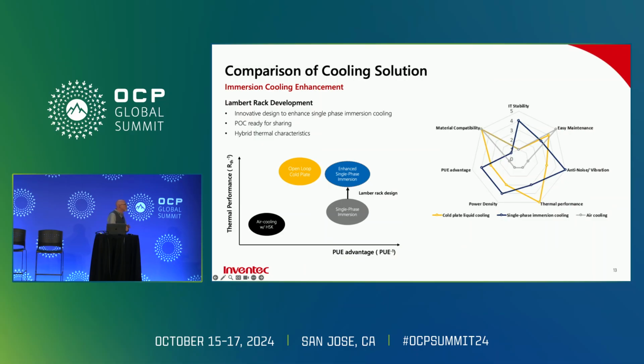As I said, we've been working with immersion cooling for the last 7 years. Immersion cooling gives us a great PUE during operation, but it can be hard to use, hard to maintain, and it's always hard to scale. Plus, immersion cooling doesn't handle some of the high thermal components as well as direct liquid cooling does.